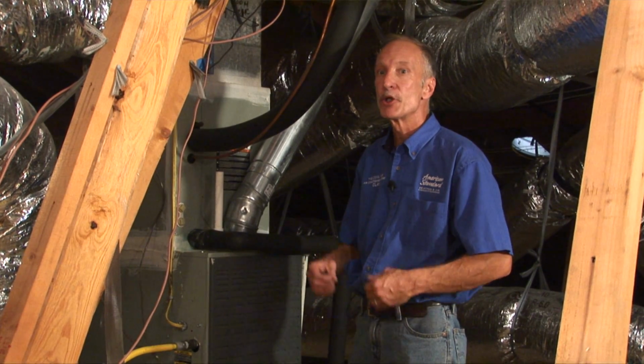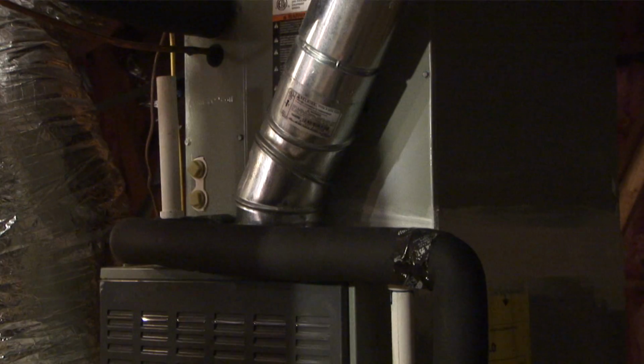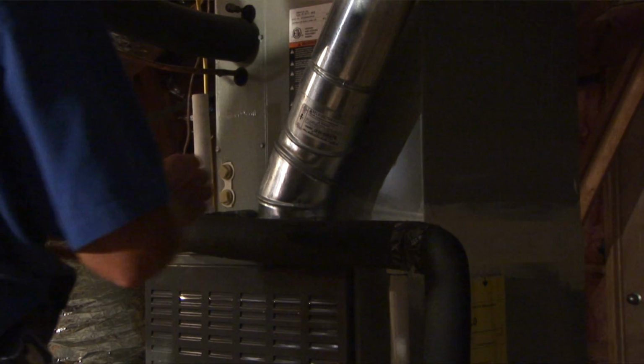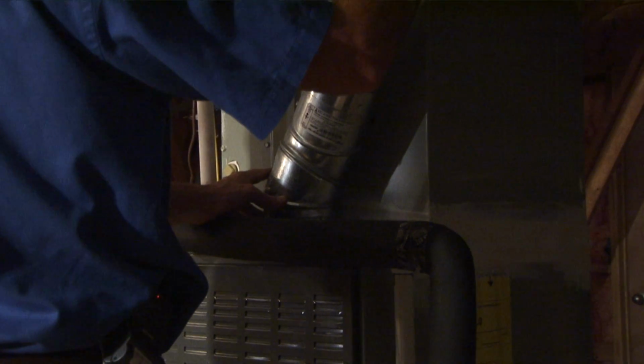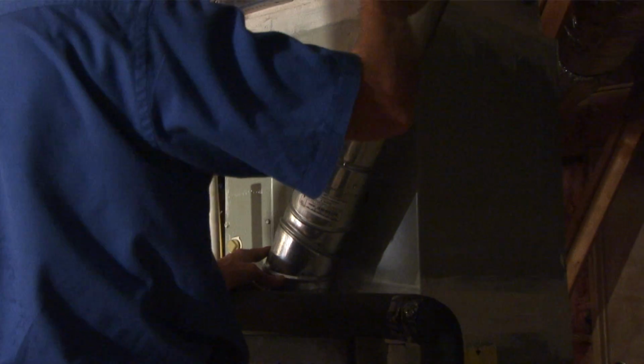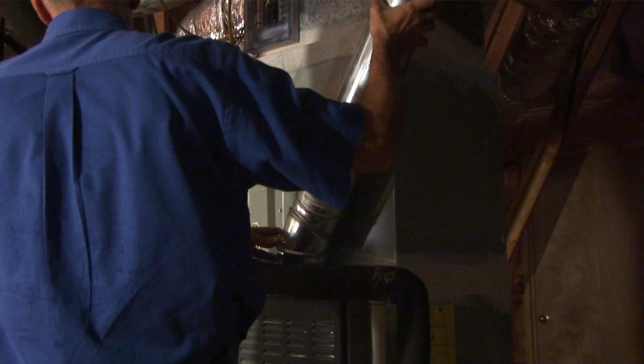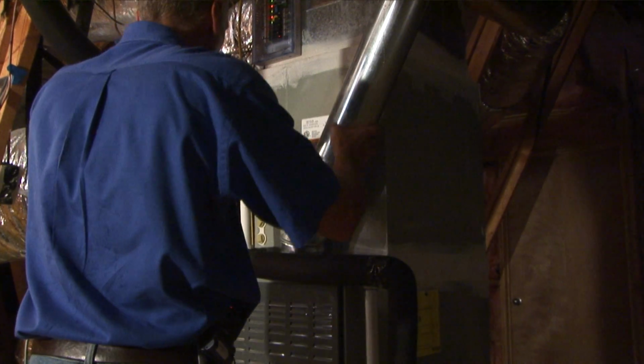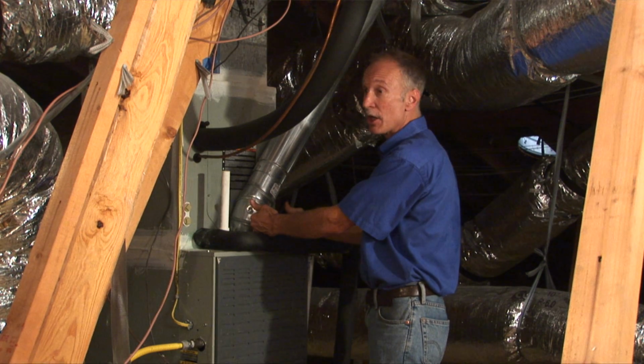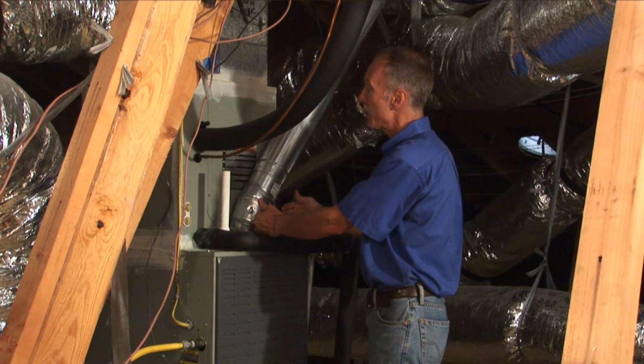Today we're going to be performing a peak performance furnace tune-up. The very first thing we do is we check the flue pipe and we make sure that it's properly vented, that it's got the proper clearance of all combustible materials, that it's sealed up and there's no leakage, which could cause an escape of carbon monoxide.